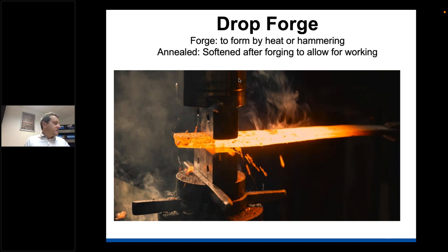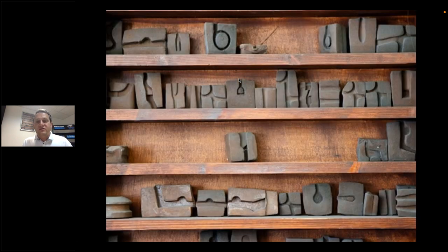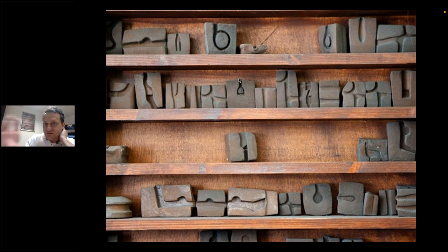Let's start from the very beginning - drop forging. This involves taking a billet of stainless steel, heating it up, and then forging it using a big power press - hammering it into shape. This is a forging of one half of a needle holder - it's been annealed to soften it, which allows you to work it. You can prove it's soft by bending it. Here we also have examples of forging bosses - the templates used during forging to achieve different shapes.